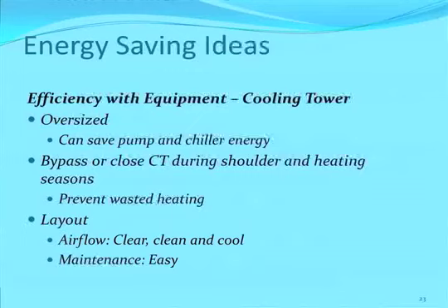You want to have a bypass that's inside your building, or at least if you're going to, when your cooling tower's on and off in your shoulder seasons, you want to be able to damper it off or prevent airflow from going through there, because even though you don't have your spray pumps going, you don't have your fans going, you'll have natural convection drawing the water out of, or the heat out of the condenser water. I had one building that I looked at that they were losing half a degree, and then it'd go back down into their building, down to their boiler, their electric boiler, so it's a direct heat impact that they're heating and cooling at the same time, and they're defeating themselves.